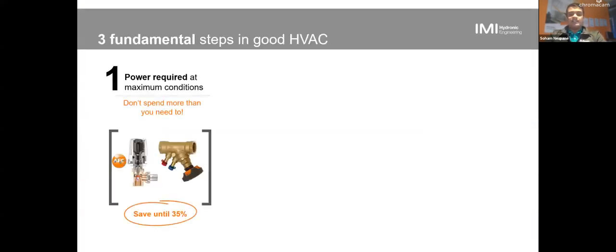So what do we do, right, to basically optimize an HVAC system? There are three basic fundamental steps we want to look at. The first one is the power required at maximum condition, and that is what balancing is about. What we want to make sure with balancing is you have the required flow rate and the power that you need for your design condition throughout your system. And you do not want to spend any more than you need to. So you want to have just the right amount, but not overflow it, right? And that can help us save up to 35% just in pumping energy. So that's a huge number when you think of a building. You have hundreds of these valves installed there.